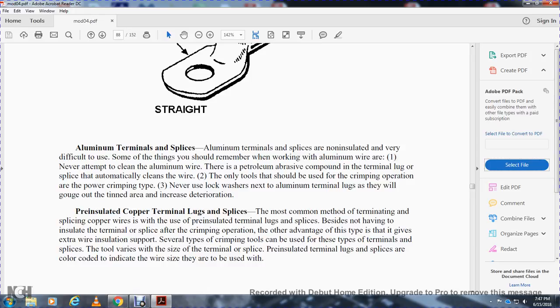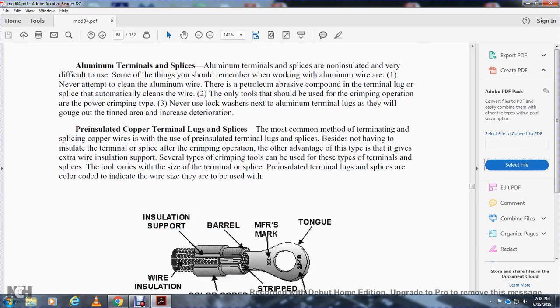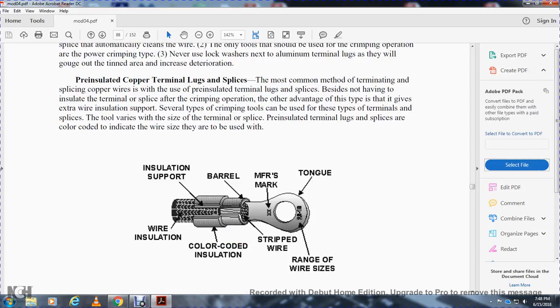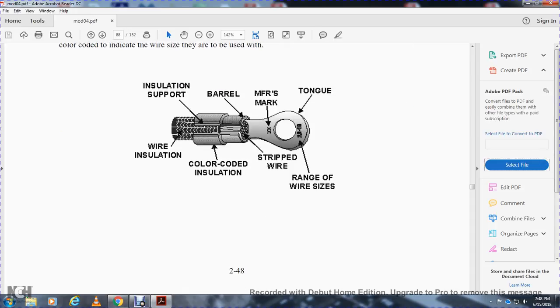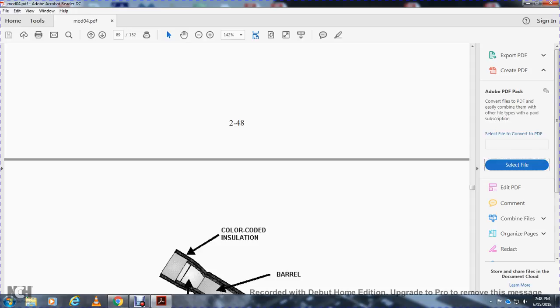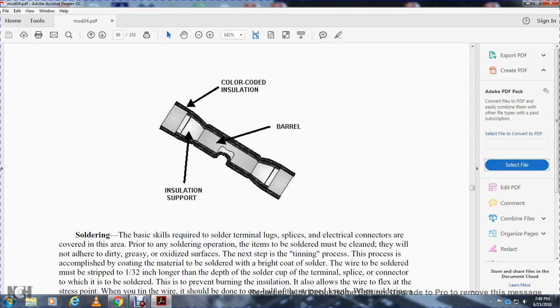Pre-insulated copper terminal lugs and splices are the most common method of terminating and splicing copper wires. The advantage is not having to insulate the terminal splice after the crimping operation. Another advantage is the extra wire insulation support. Some types of crimping tools can be used on the terminals and splices with the tools placed over the side of the terminal splice. Pre-insulated terminal lugs and splices are color coded to indicate the wire size. Components include wire insulation, insulation support, the barrel, color coded insulation, the manufacturer's wire strip gauge, and the tongue. The range of wire size is also printed on the color coded insulation.